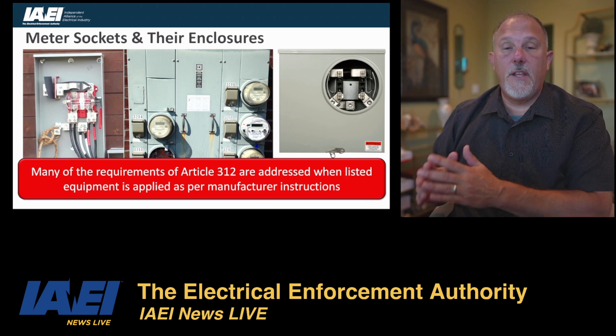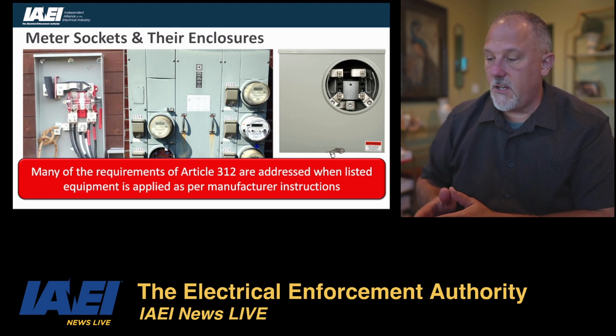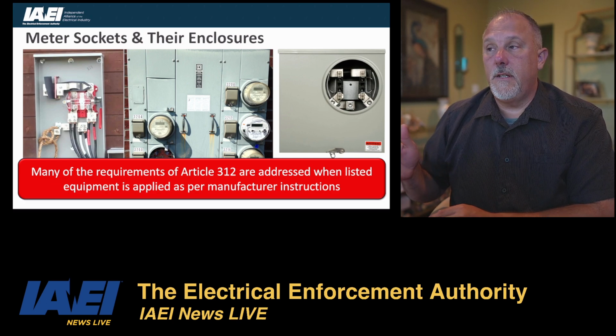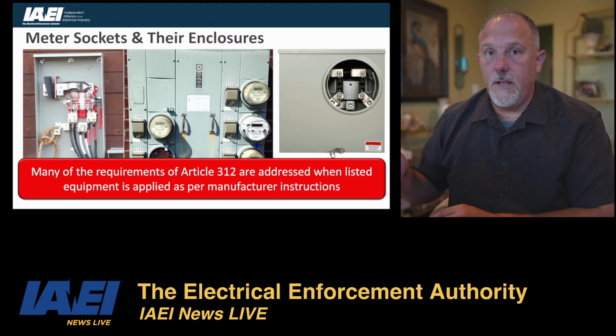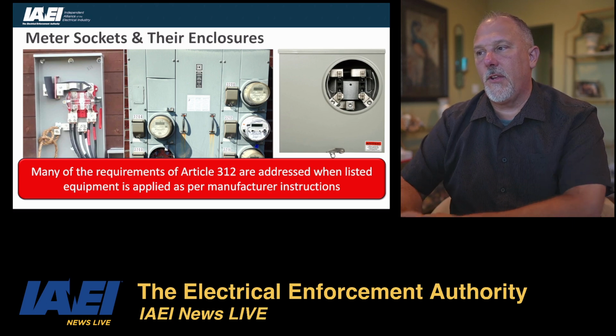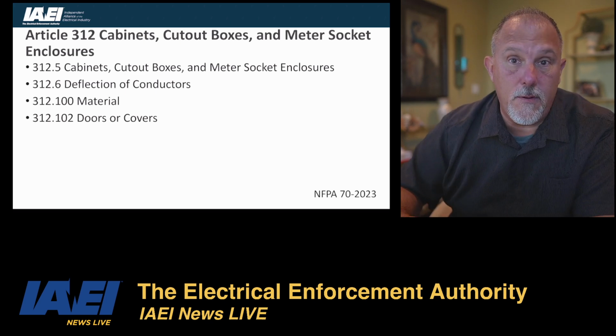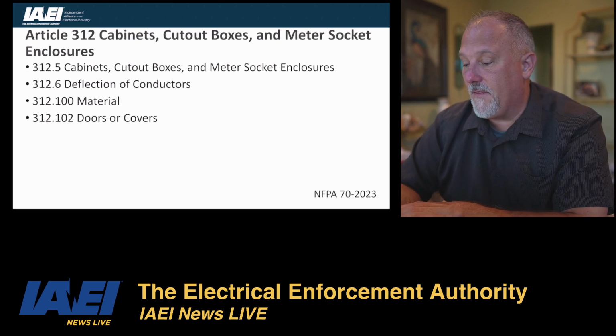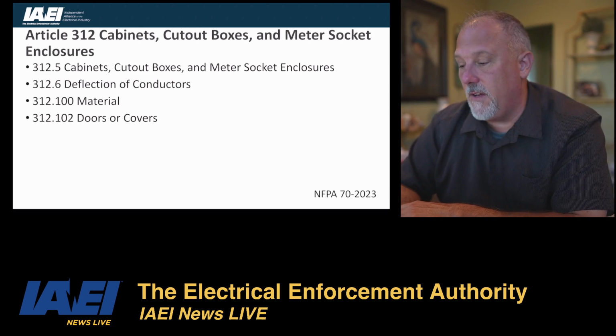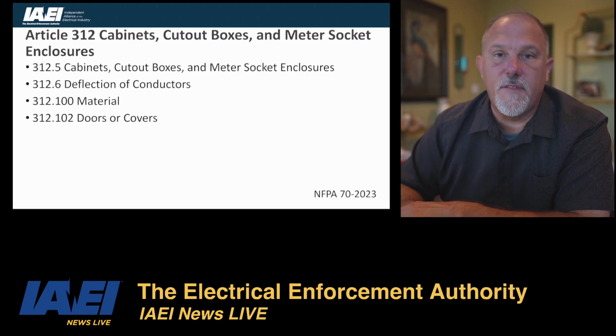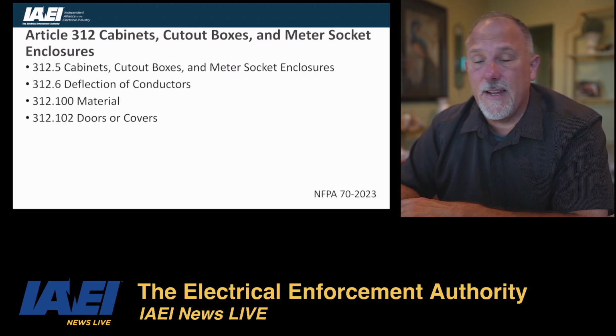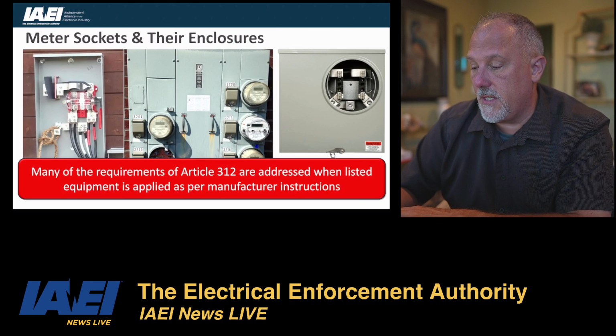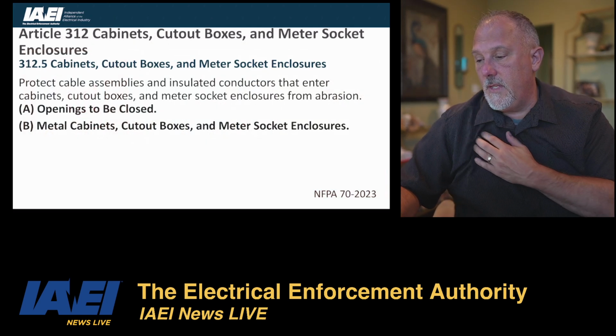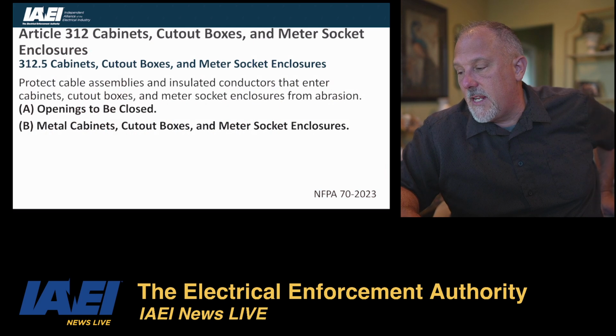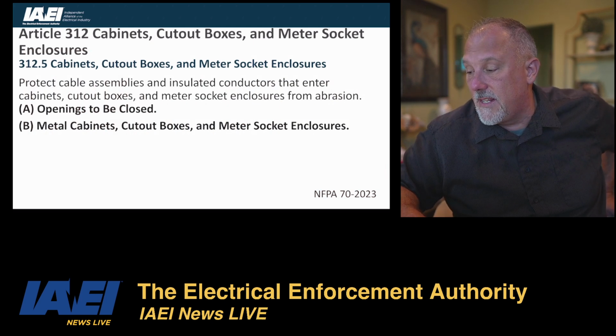So if it is service equipment, if it's a service meter socket, and it is not owned by the utility, it's required to be listed, and I would argue that the material is going to be part of the listing. The fact that it has a door or a cover is going to be part of the listing. When it comes to deflection of conductors and how they're installed, I can definitely see that being part of the installation process.